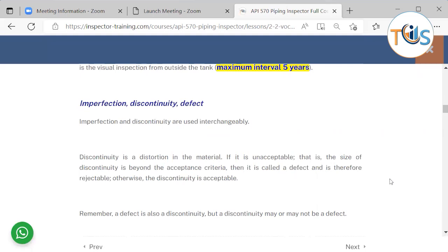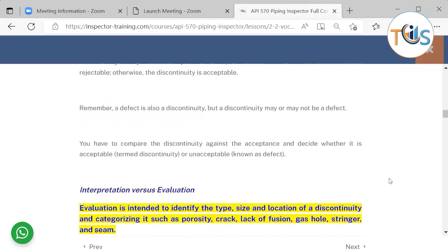Acceptance criteria refers to the maximum allowable limit for a type of discontinuity. If a discontinuity is below that threshold, it is acceptable. Remember that a defect is a discontinuity, but a discontinuity may or may not be a defect depending on whether it exceeds the acceptance criteria. You compare a discontinuity against the acceptance criteria and decide whether it is acceptable — termed a discontinuity — or unacceptable, which is known as a defect. This process is called interpretation.